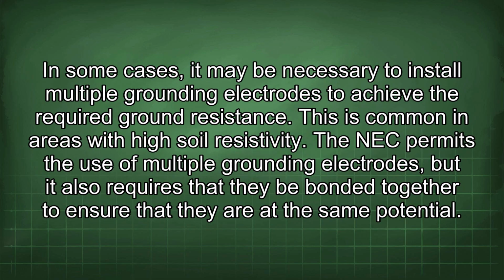In some cases, it may be necessary to install multiple grounding electrodes to achieve the required ground resistance. This is common in areas with high soil resistivity. The NEC permits the use of multiple grounding electrodes, but it also requires that they be bonded together to ensure that they are at the same potential.